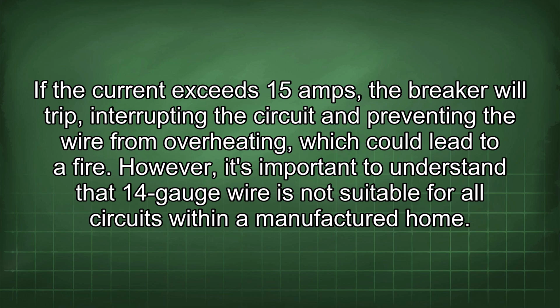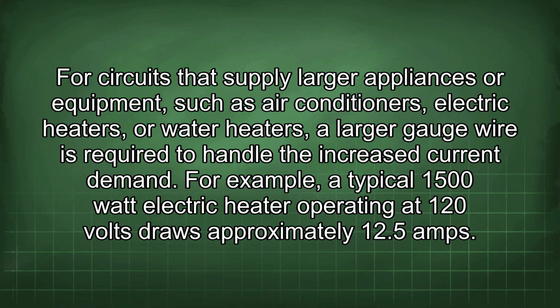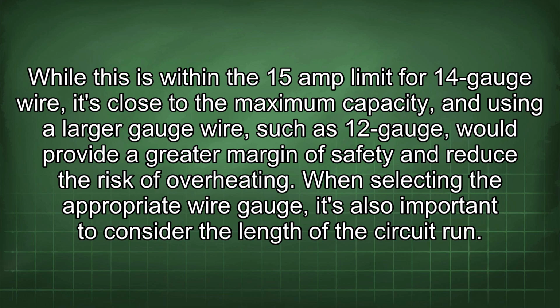However, it's important to understand that 14-gauge wire is not suitable for all circuits within a manufactured home. For circuits that supply larger appliances or equipment, such as air conditioners, electric heaters, or water heaters, a larger gauge wire is required to handle the increased current demand. For example, a typical 1500-watt electric heater operating at 120 volts draws approximately 12.5 amps. While this is within the 15-amp limit for 14-gauge wire, it's close to the maximum capacity, and using a larger gauge wire, such as 12-gauge, would provide a greater margin of safety and reduce the risk of overheating.